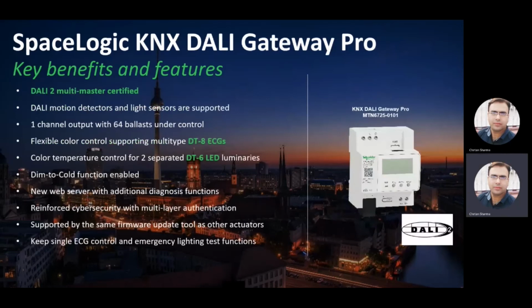Third one is the SpaceLogic KNX DALI Gateway Pro. This is a DALI 2 multi-master certified device. We can connect DALI based motion sensors, light sensors, as well as other DALI based devices with this gateway. Again, a standard one channel DALI gateway, which can control up to 64 ballasts, and all features like flexible color control by using DT8, color temperature control by using 2 separate DT6 luminaires, dim to cool functions, web server based control with additional diagnostic features, and many more.